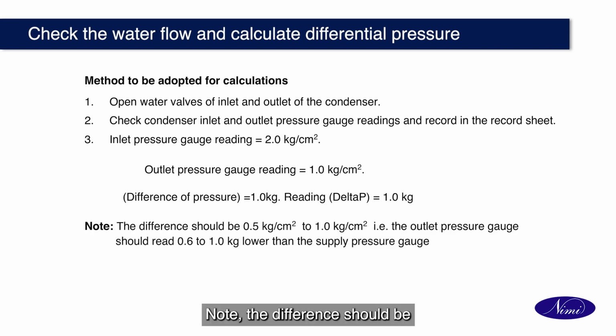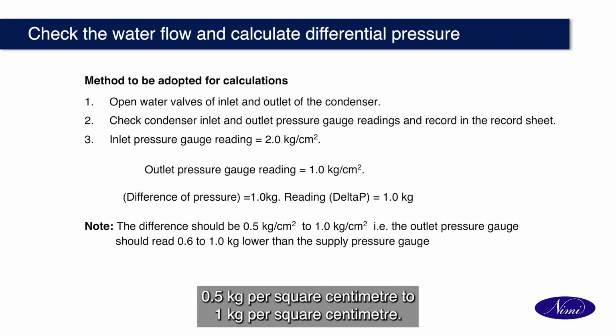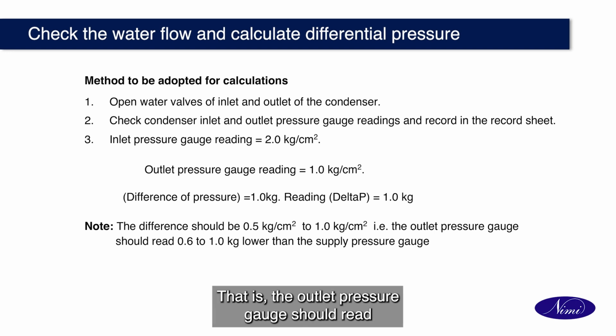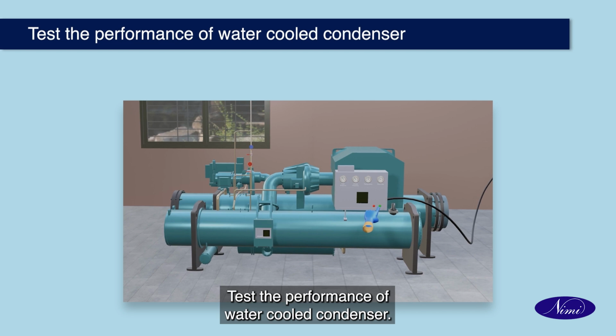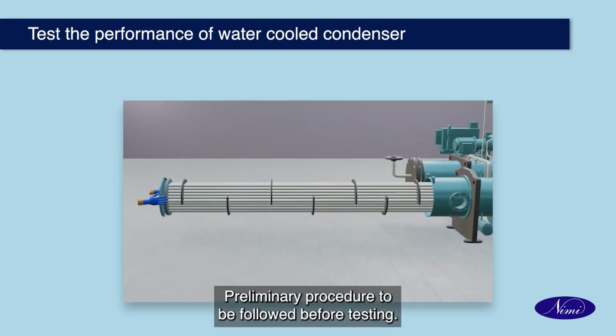Note: the difference should be 0.5 kg per square centimeter to 1 kg per square centimeter. That is, outlet pressure gauge should read 0.6 to 1 kg lower than the supply pressure gauge. Test the performance of water-cooled condenser. Preliminary procedure to be followed before testing.